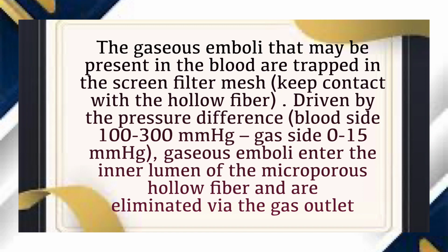The gaseous emboli that may be present in the blood are trapped in the screen filter mesh keep contact with the hollow fiber, driven by the pressure difference, blood side 100 to 300 mmHg. On the gas side, gaseous emboli enter the inner lumen of the microporous hollow fiber and are eliminated via the gas outlet.